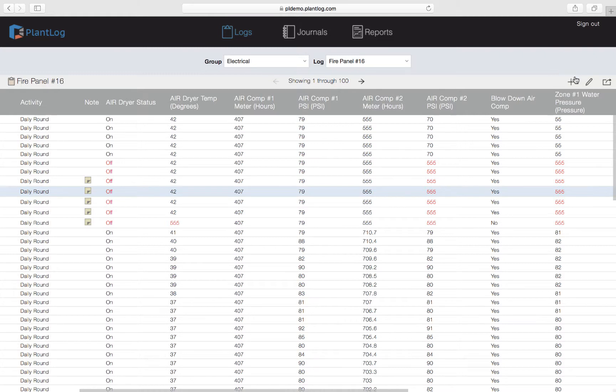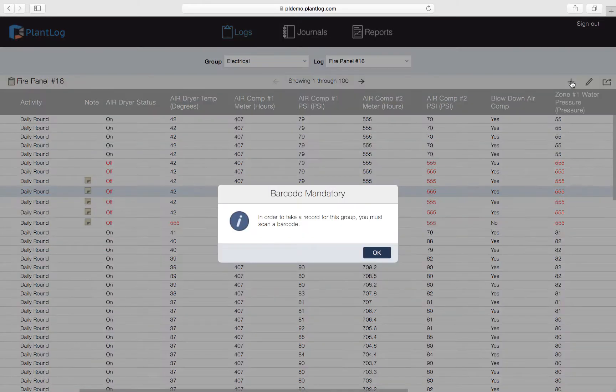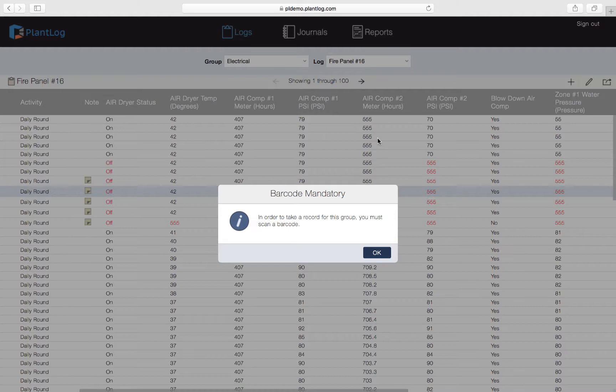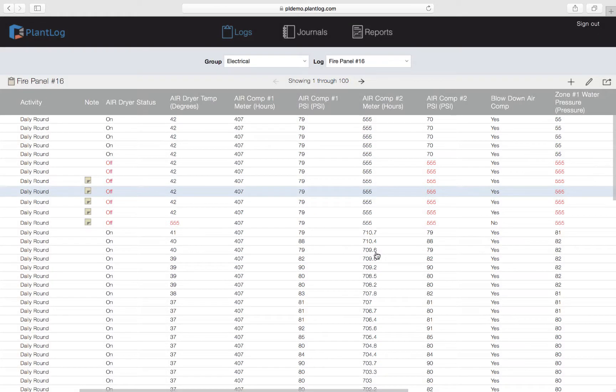We'll come up to the toolbar and hit the plus button in the upper right corner and click on Add Record. We're seeing a message that says Barcode Mandatory. The administrator of this software is telling us that for this particular log — Fire Panel Number 16 — they do not want the record recorded from the web application; instead they require a barcode to be scanned. Barcode scanning is only supported in the mobile app, so we cannot create a record here for this log in the web application. When barcode mandatory is set, it must be done from the mobile app, as the desktop web browser has no means to scan a barcode on a physical asset.